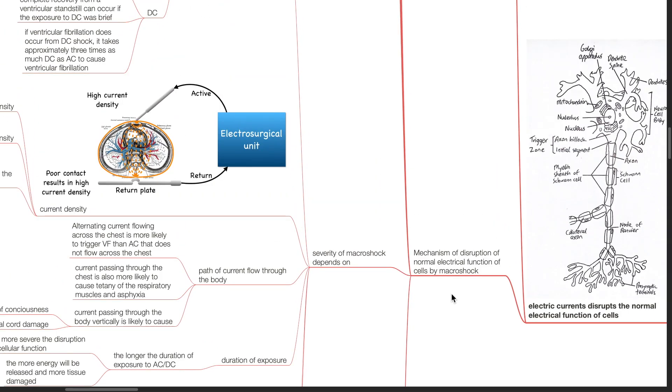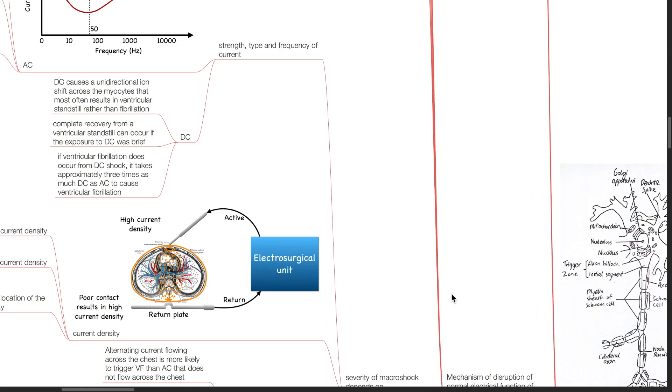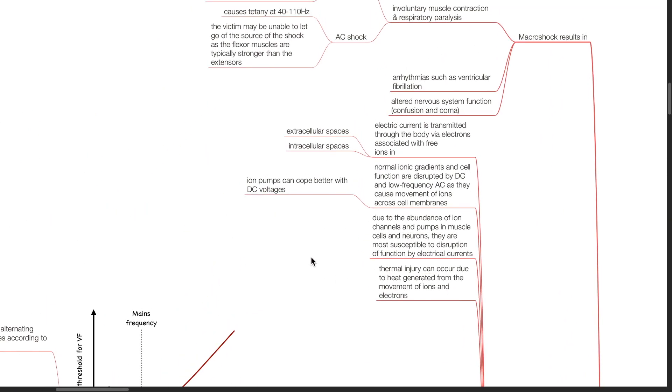Mechanism of disruption of normal electrical function of cells by macroshock. Electric current is transmitted through the body via electrons associated with free ions in extracellular and intracellular spaces. Normal ionic gradients and cell functions are disrupted by DC and low-frequency AC, as they cause movement of ions across cell membranes. Ion pumps can cope better with DC voltages compared to AC voltages. Due to the abundance of ion channels and pumps in muscle cells and neurons, they are most susceptible to disruption of function by electrical currents. Thermal injury can occur due to the heat generated from the movement of ions and electrons.